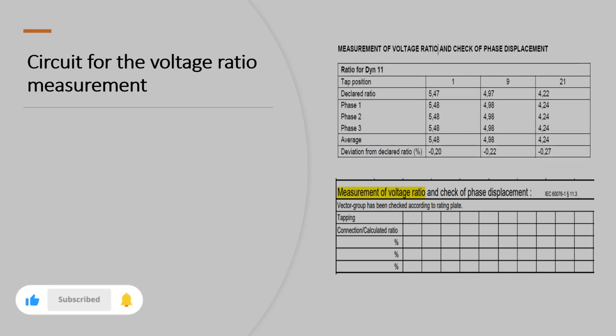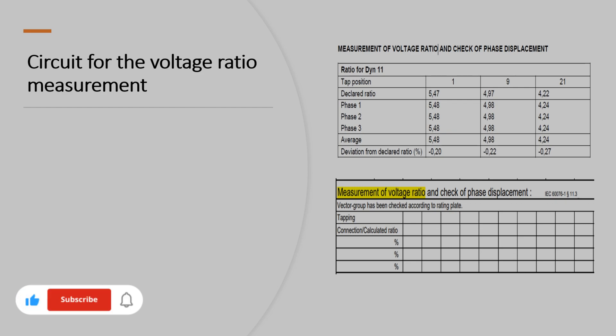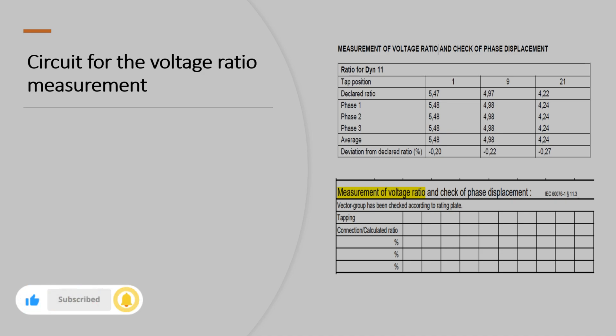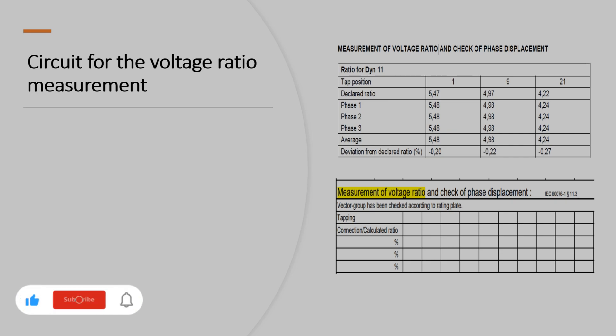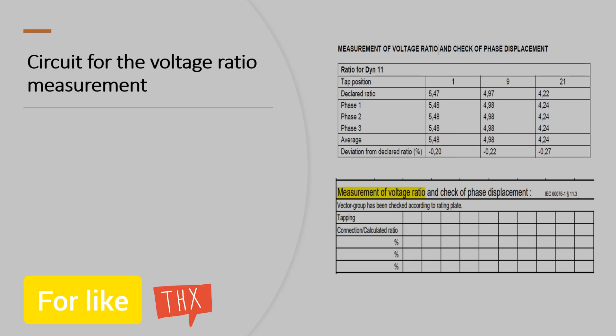We are using the IEC standard. For measuring voltage ratio and checking phase displacement — this is the ratio for dyn11, which is our vector group, at tap position. The declared ratio is shown here: tap positions 1, 9, and 21, as seen in the previous slide. The declared ratio is broken down by phase one, phase two, phase three, and then average and deviations of the declared ratio.